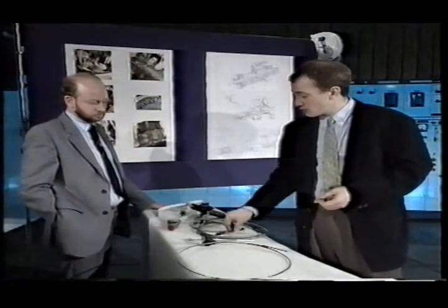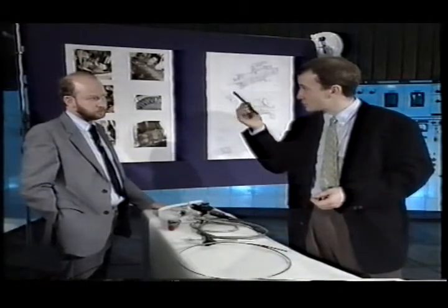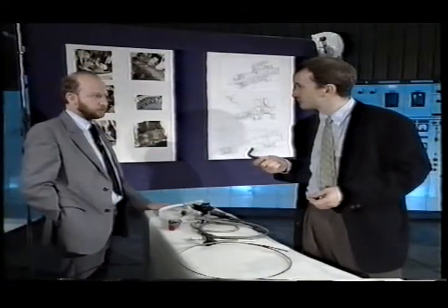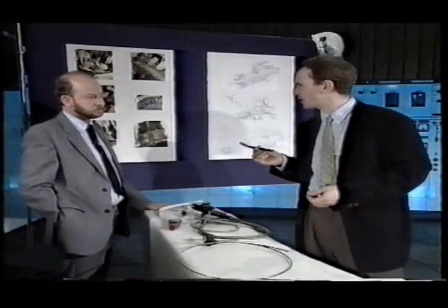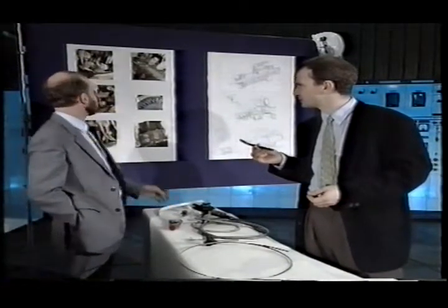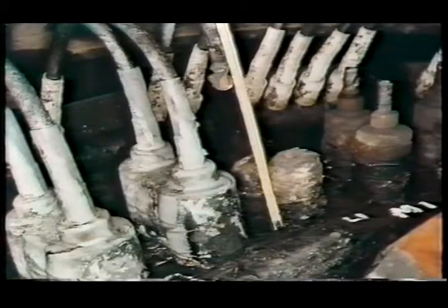I'm joined now by Nick Plant, who has investigated the cause of many machine failures. So, Nick, what would have been the result of this being left in the machine? Well, the probable result would have been the ejection of the Allen key from the fan at high speed straight into the stator end winding. And what sort of damage might that cause? Well, we can see on these photographs here some typical damage, and the subsequent failure has completely wrecked the machine.